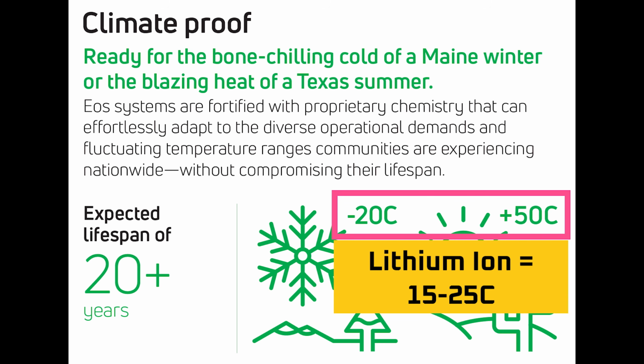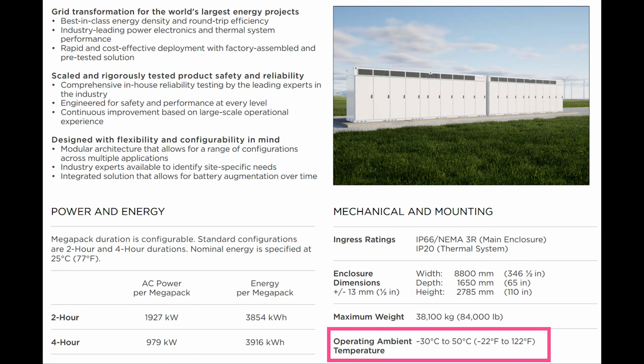Although EOS batteries can operate in a wider temperature range than lithium-ion batteries at a chemistry level, -20 to 50 degrees Celsius versus 15 to 25 degrees Celsius, the thermal management system that comes with grid-scale lithium-ion batteries means they can operate at an even broader temperature range than the Z3, from -30 to 50 degrees Celsius. So the end product of each chemistry operates within a similar temperature range.